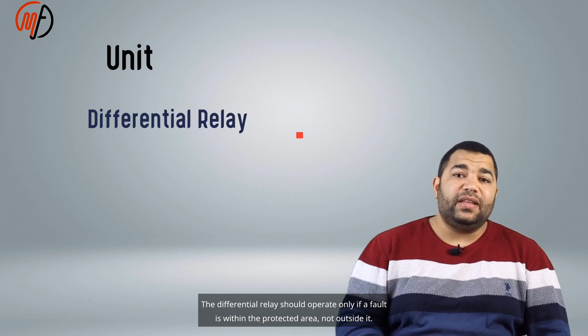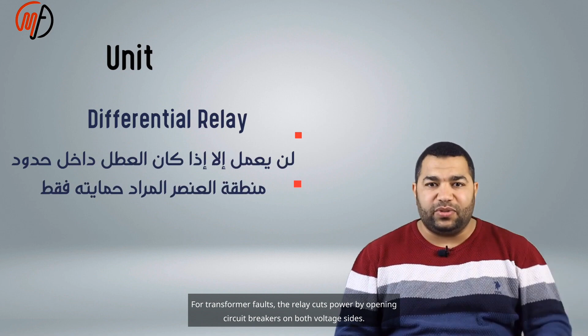The differential relay should operate only if a fault is within the protected area, not outside it. For transformer faults, the relay cuts power by opening circuit breakers on both voltage sides. For line faults, the line's differential protection isolates the line by opening local and remote breakers. For bus bar faults, the bus bar's protection disconnects all potential feeders. These protections are independent. Generator protection differs in two ways.